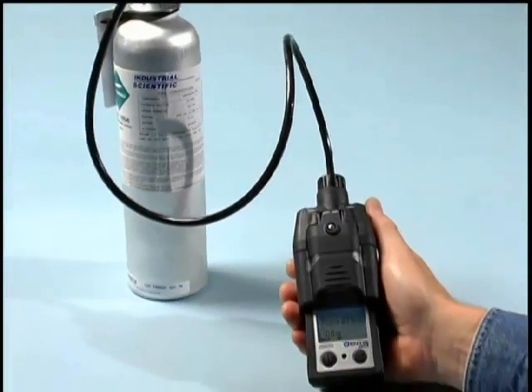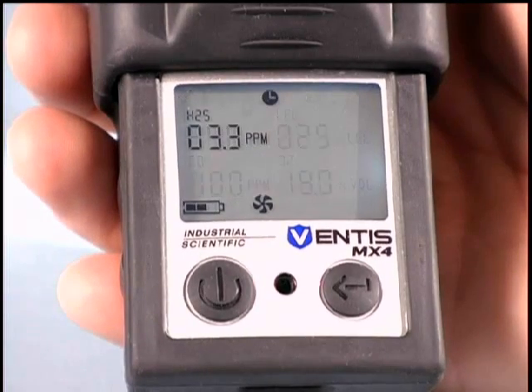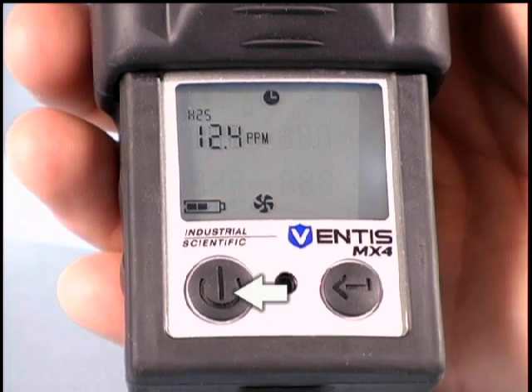The bump test process for the Ventis MX4 is easy and automatic. The display will prompt you what gases to apply and at what time. To skip a specific sensor at any time during its bump test, just press the on-off mode button to go to the next sensor.